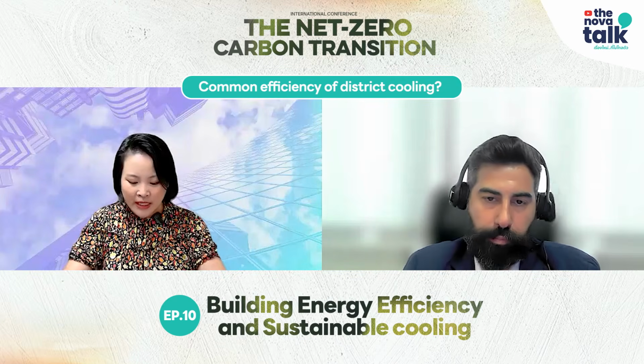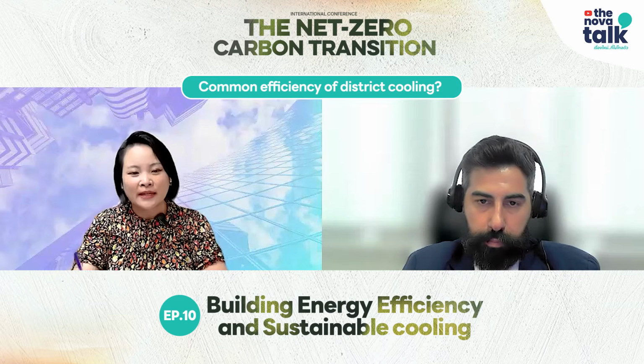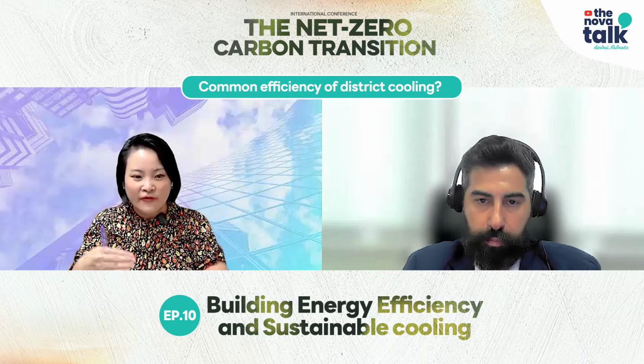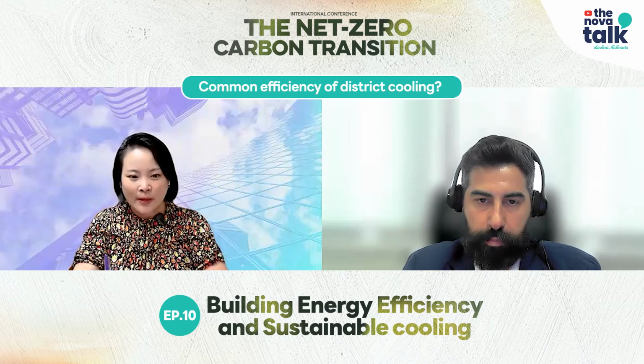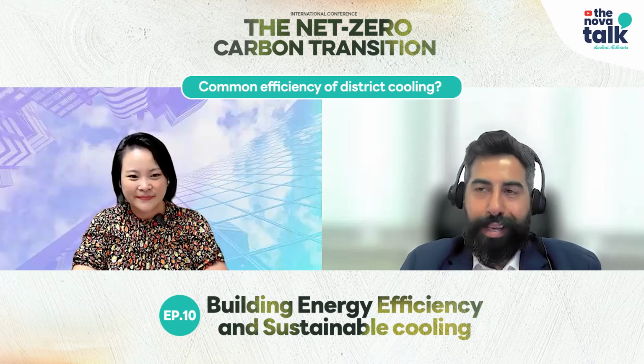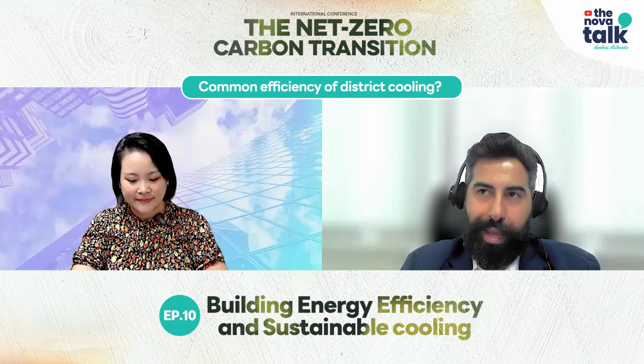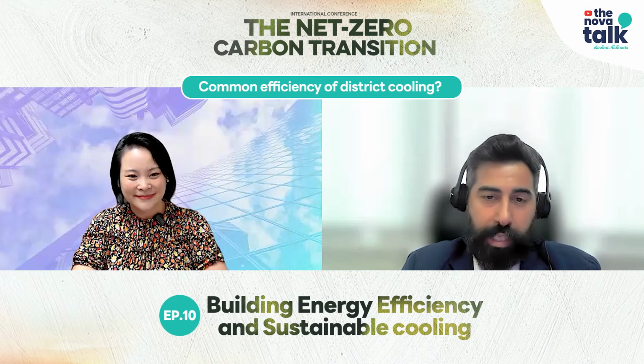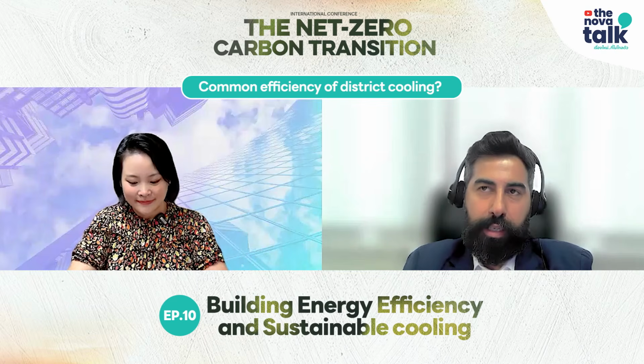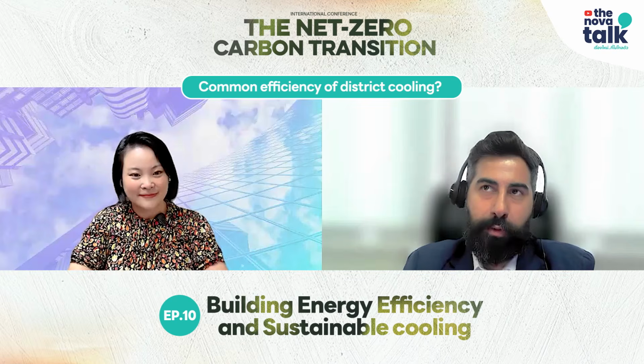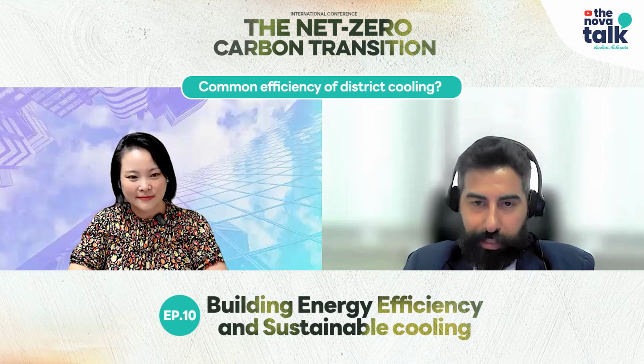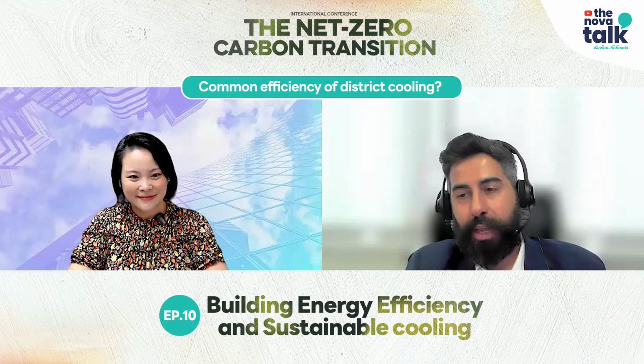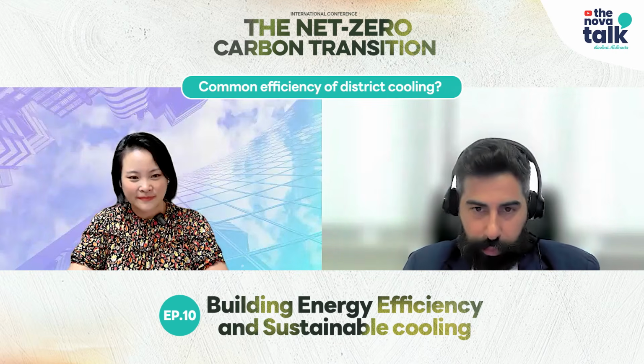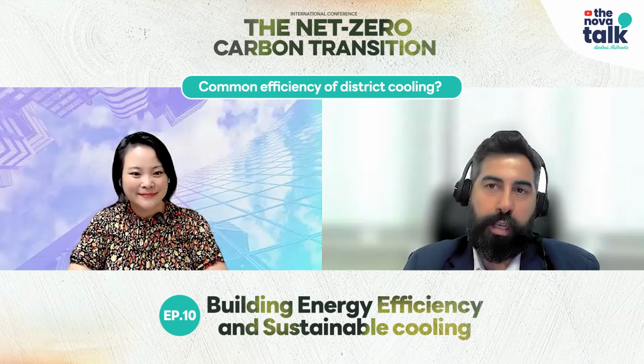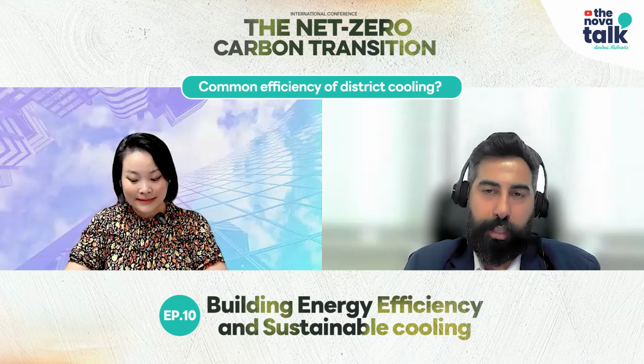The next question would be, would you recommend the typical or common efficiency of a district cooling plant, kilowatt per ton? Currently, we're designing a plant to be around 0.7 kilowatt per ton. However, the information needed to answer that question is, if you were looking at Thailand, you have a constant high wet bulb. So your efficiency will need to be adjusted accordingly.